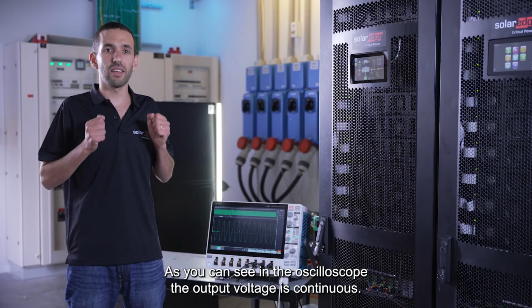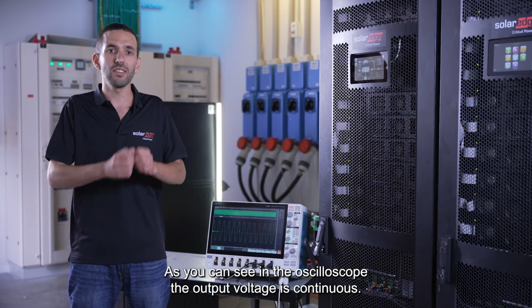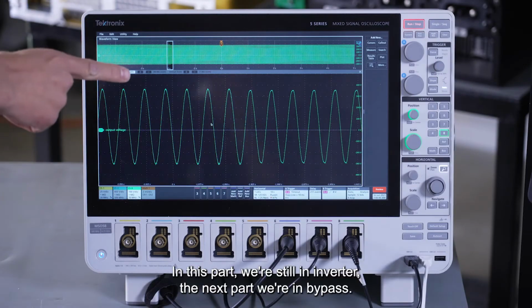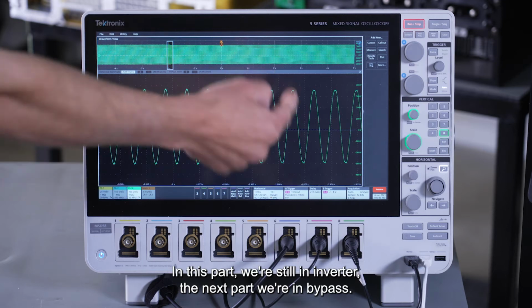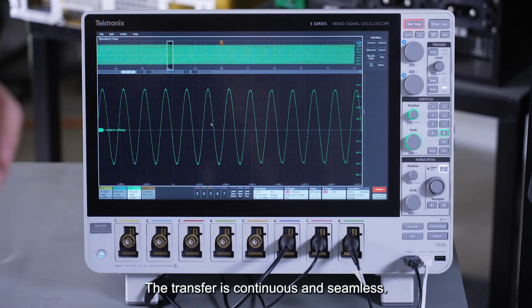As you can see in the oscilloscope, the output voltage is continuous. In this part, we're still in inverter. The next part, we're in bypass. The transfer is continuous and seamless.